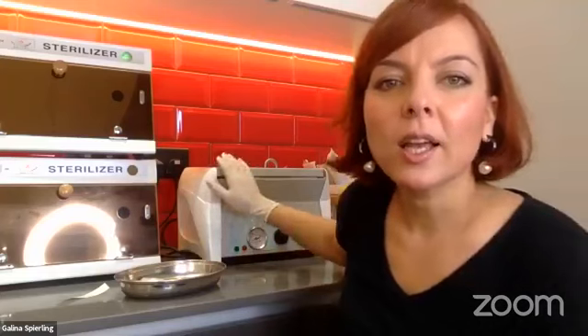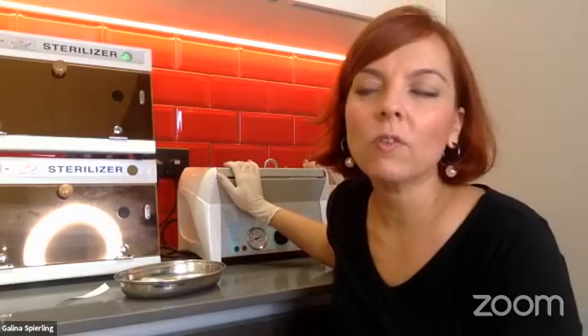Also, hairstylists are normally scared. Unfortunately, I don't have my scissors here to show. They are normally scared of the ball bearing being affected by the liquid disinfectants. Plus, for most successful hairstylists, shears cost about 1,000 dirhams and above per piece. So yes, shears can be sanitized, disinfected, and sterilized as well, as long as you are using the correct disinfectant and the temperature that is prescribed by the manufacturer. Normally, everything dies here in this hot stove at a temperature above 140 degrees.